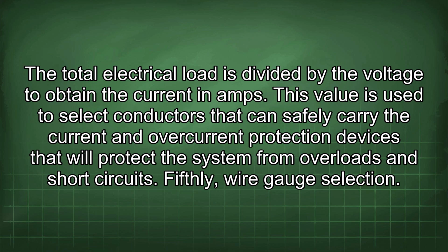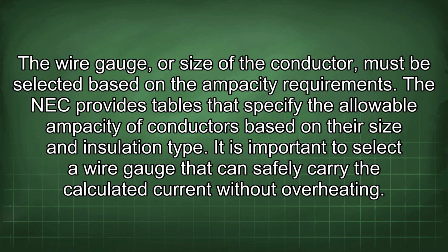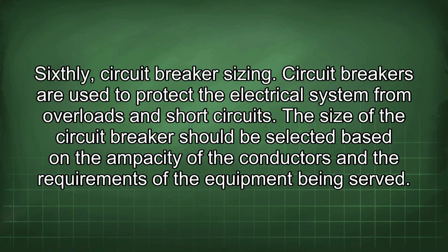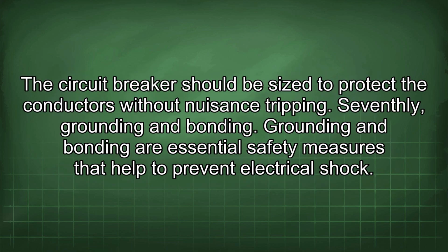Fifthly, wire gauge selection. The wire gauge, or size of the conductor, must be selected based on the ampacity requirements. The NEC provides tables that specify the allowable ampacity of conductors based on their size and insulation type. It is important to select a wire gauge that can safely carry the calculated current without overheating. Sixthly, circuit breaker sizing. Circuit breakers are used to protect the electrical system from overloads and short circuits. The size of the circuit breaker should be selected based on the ampacity of the conductors and the requirements of the equipment being served. The circuit breaker should be sized to protect the conductors without nuisance tripping.